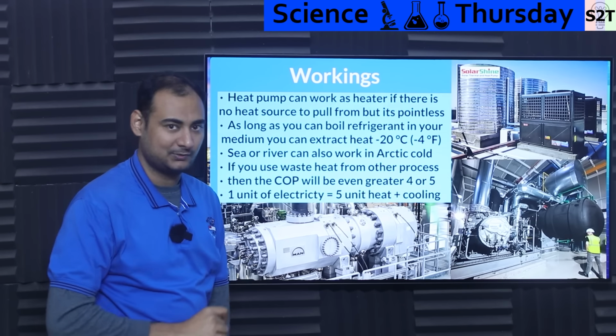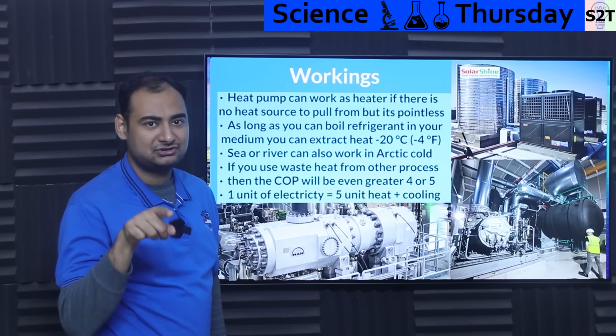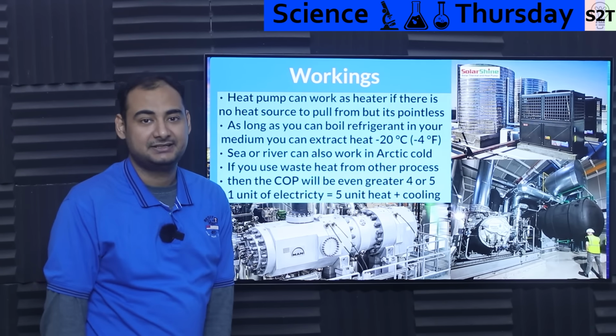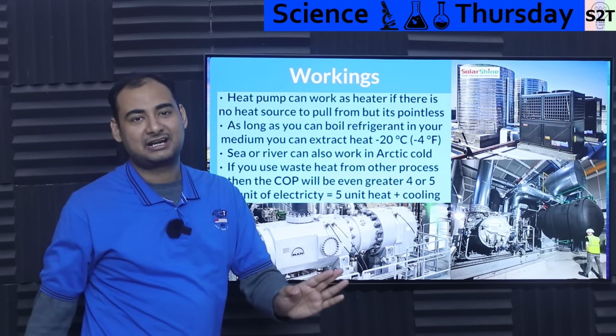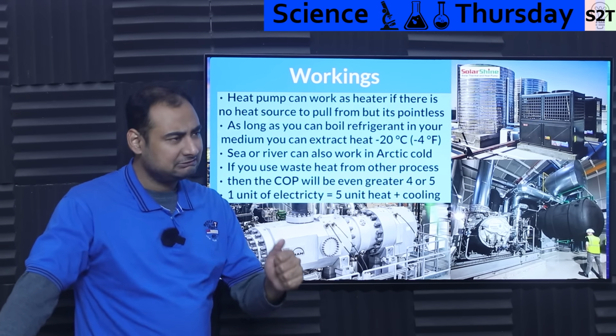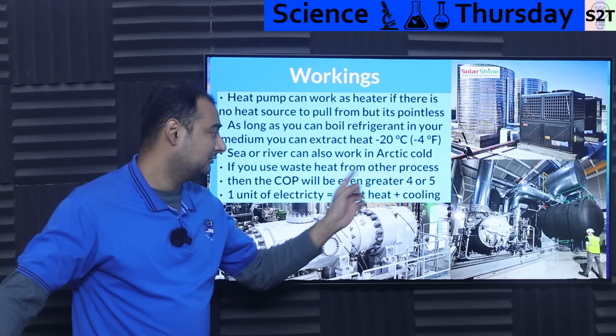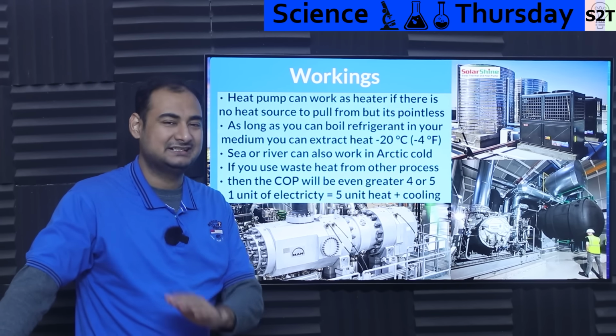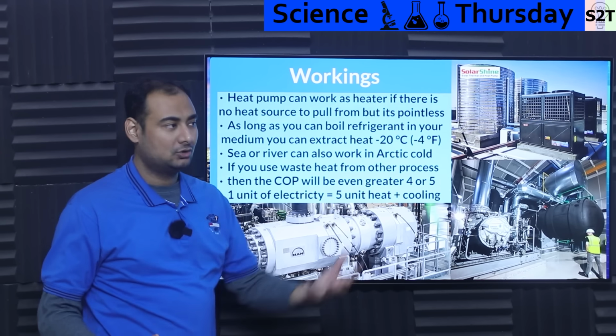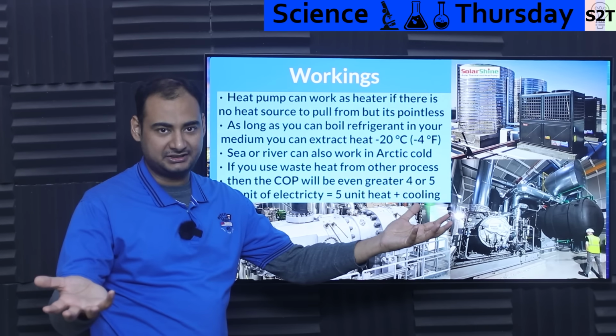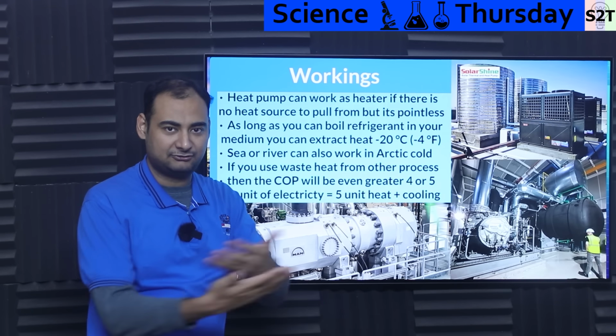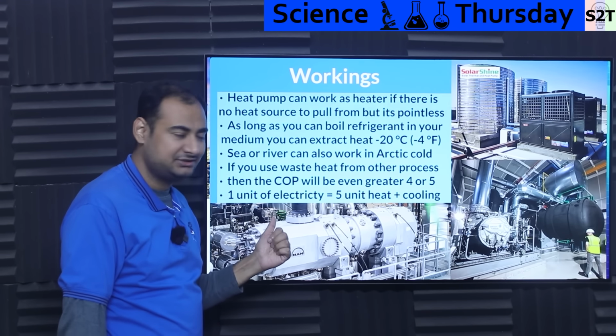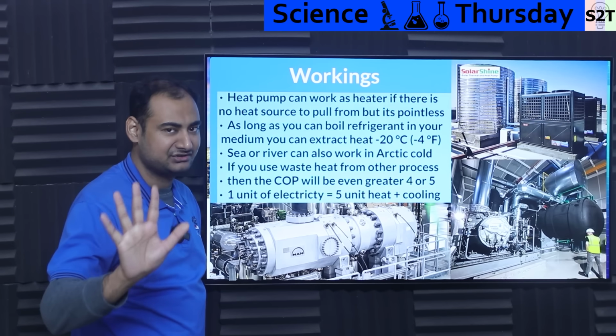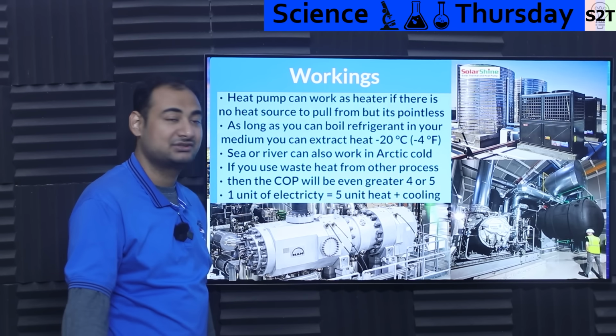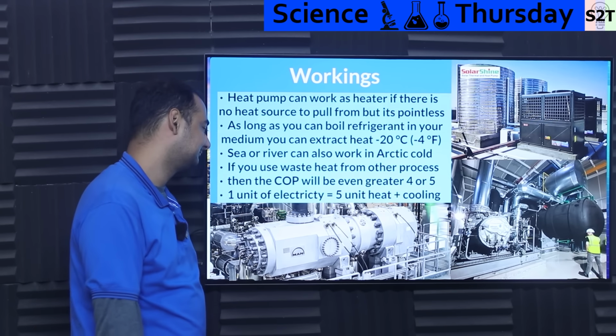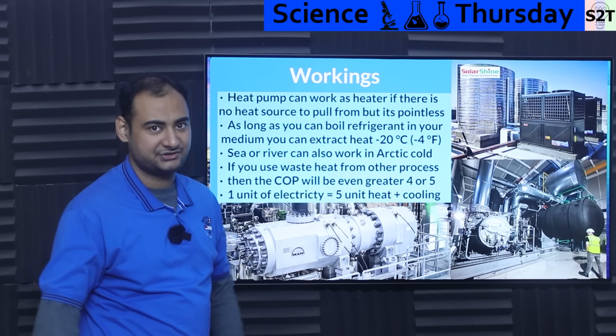Waste heat, that's your sweet spot. We have to close the loop. The moment you close the loop, you can get 4 or 5 COP. That's easy. And at that COP, just stop the discussion. 2 COP, okay. 3 COP, good. 4 or 5, stop discussion. Meaning, if you have a data center and you want district heating, that's a perfect couple for each other. One unit of electricity you dump into the compressors can give you 5 units of heat. It's perfect. And again, you can cascade it if you need very high temperature.